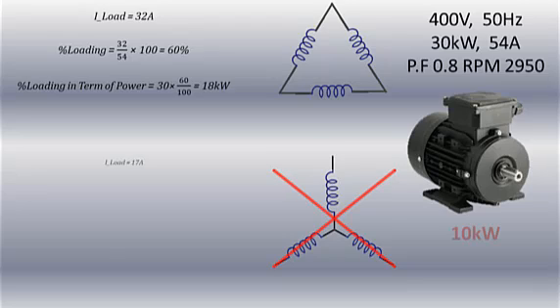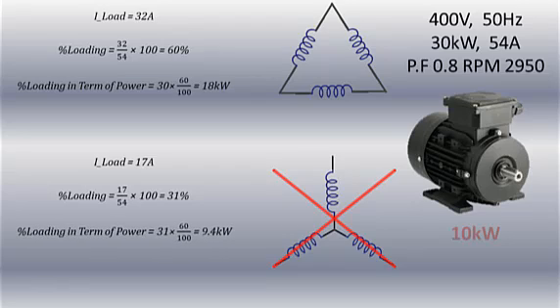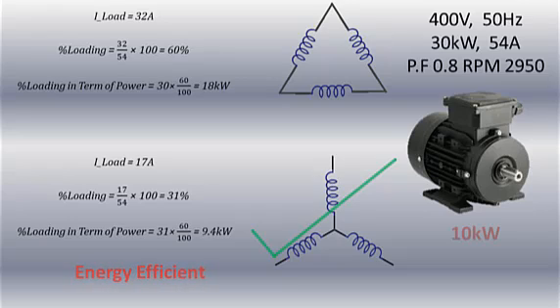However, if the motor is drawing 17 ampere, which is 31 percent of its rated current, the motor will be running at 31 percent of its rated power, which is approximately 9.4 kilowatt. Since this is less than 10 kilowatt, running the motor in star configuration will be safe, and it will also be more energy efficient compared to delta connection.